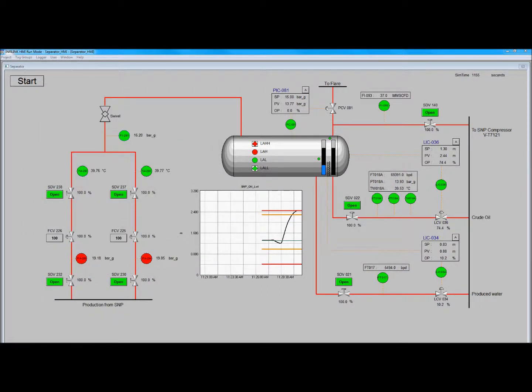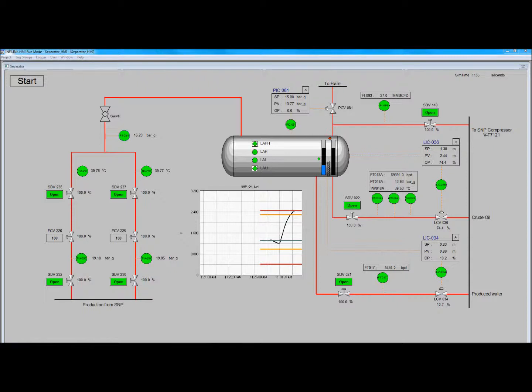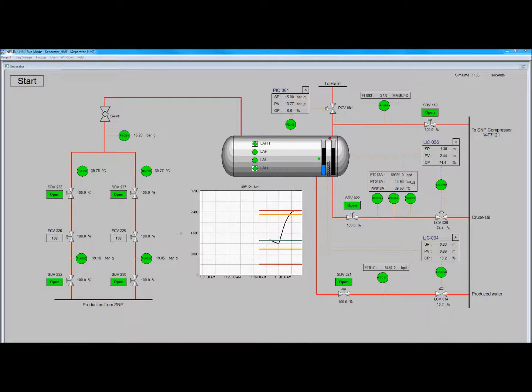Ideally, the user will learn, firstly, that low pressure alarms at the riser indicate a loss of gas lift, which will be followed by severe slugging. If no action is taken, the oil level in the separator will increase until LAHH trip occurs, which is a bad thing.